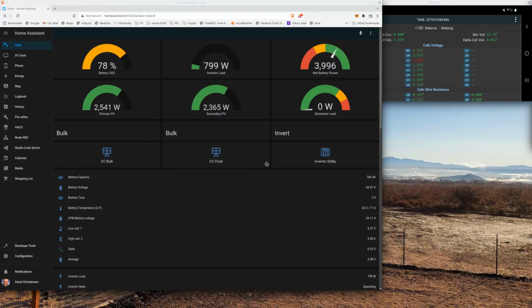Sometimes if I'm not running enough loads, the state of charge will get to 100%. I've derated these batteries — there's technically 1,088 amp hours, but I've knocked them down to about 980 as far as what the system thinks 100% charge is. So there's some leeway built in there.